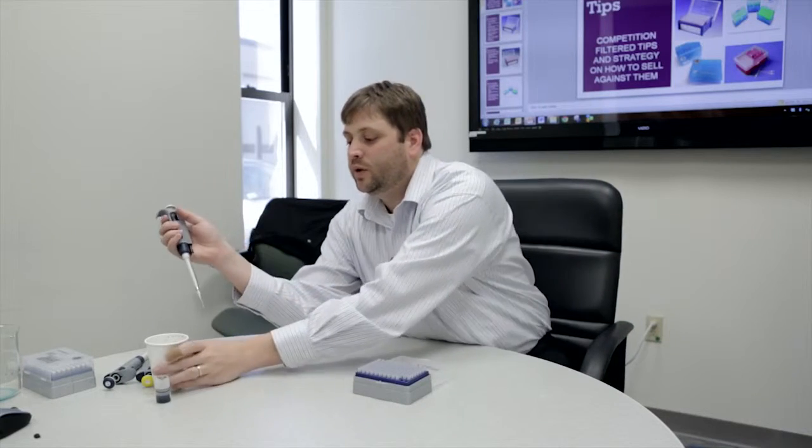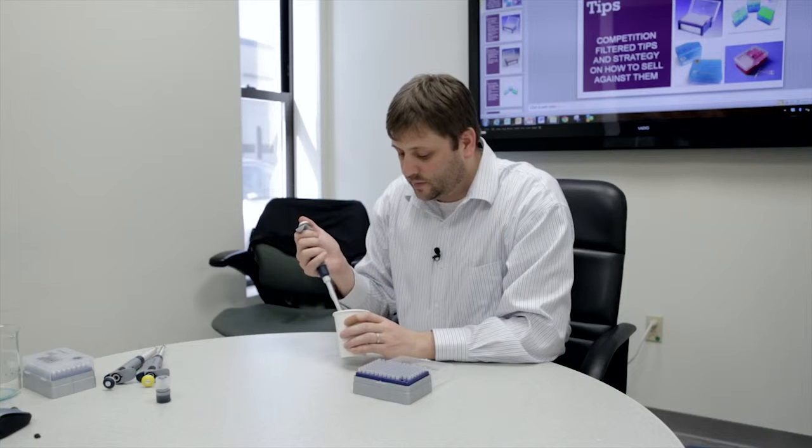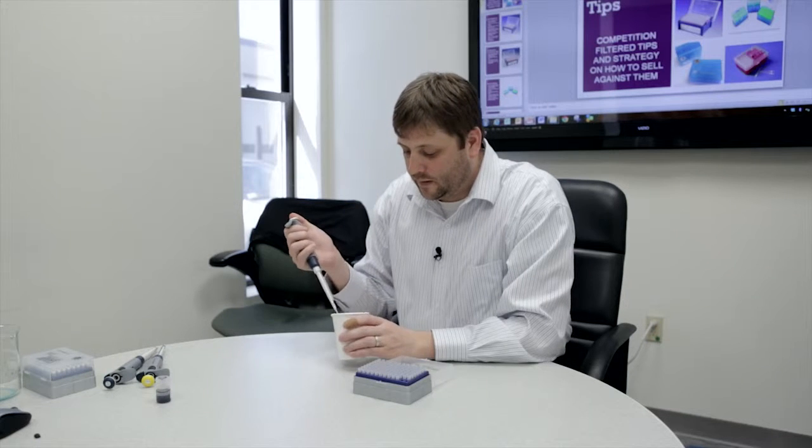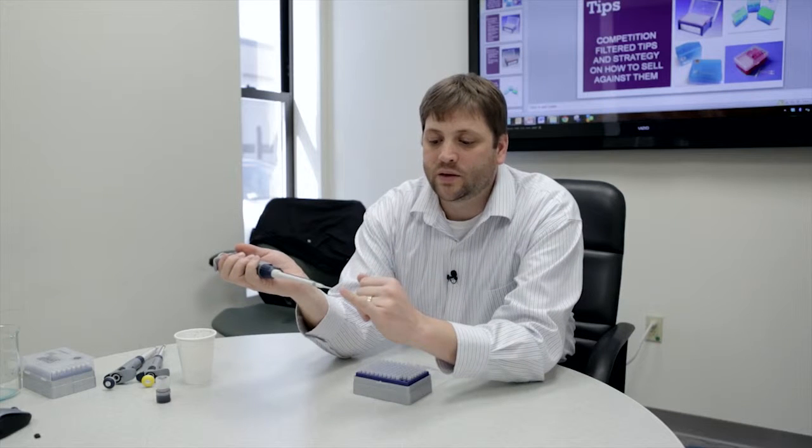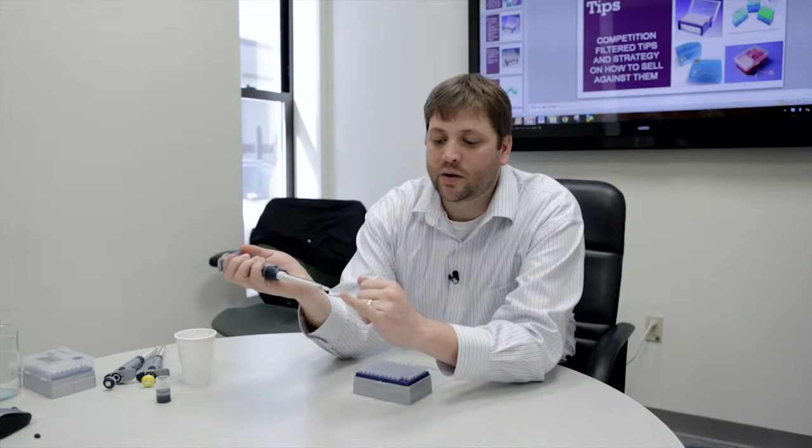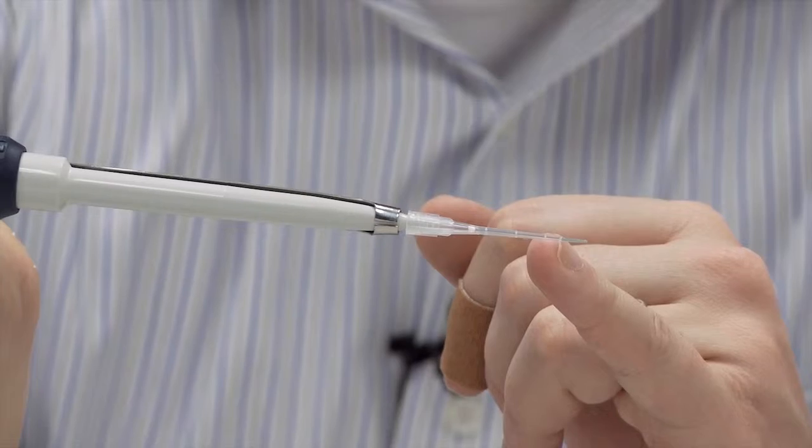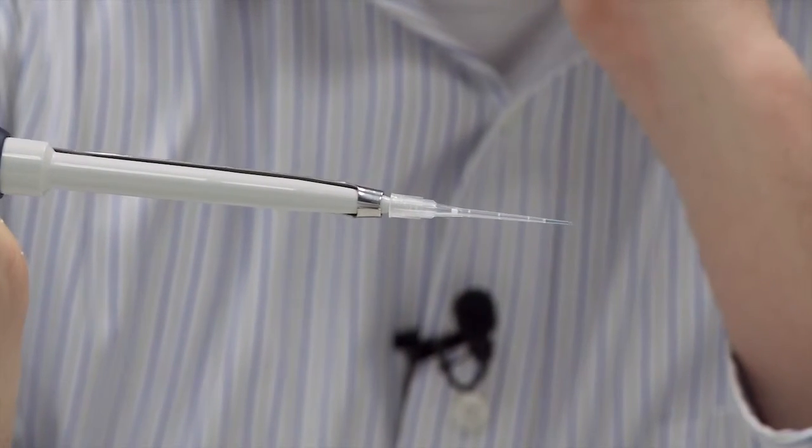And just to show you exactly what that means. This is just a dyed water, and as you can see I've taken a 1 microliter draw with our Denville pipetter, and you can see it goes right to the 1 microliter accuracy mark.